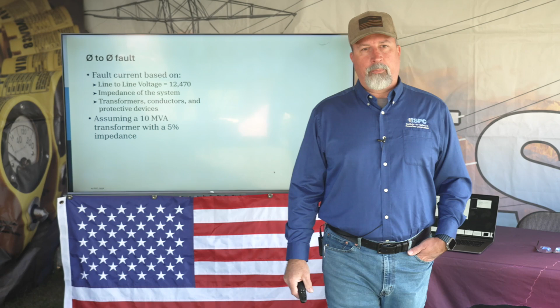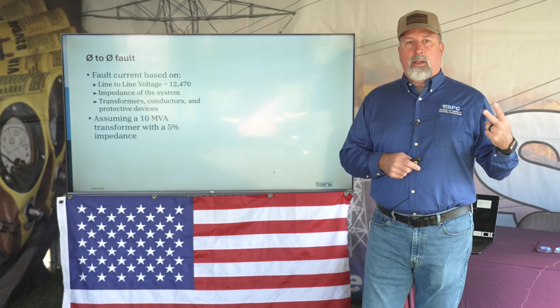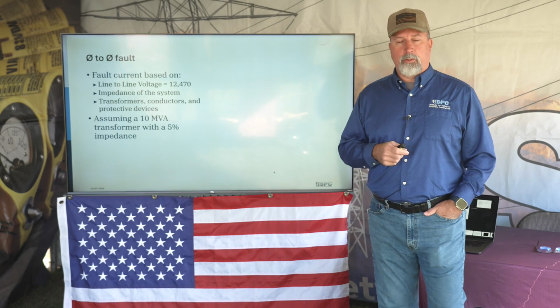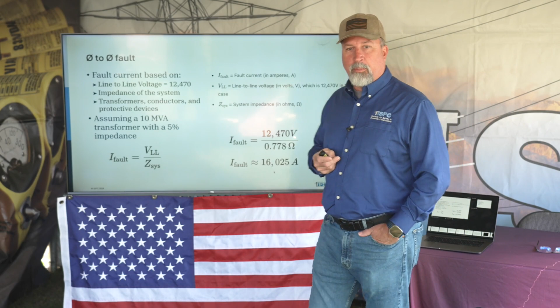So here's another calculation, fault current based on a line-to-line voltage of 12,470, right? A very common voltage that we work on in our distribution systems, right? It's also based on the impedance of the system, and then the transformers, conductors, and protective devices, right? It all plays into the equation of how much current you're going to be susceptible to. So assuming just a standard 10 MVA transformer with a 5% impedance, okay? In order to figure out what fault current could be in that configuration, should something happen, you take the voltage line to line divided by the system impedance, right? So 12,470, you divide it by that 5% impedance, which is 0.778 ohms, and you can see that the fault current in that situation is going to be north of 16,000 amps, okay?